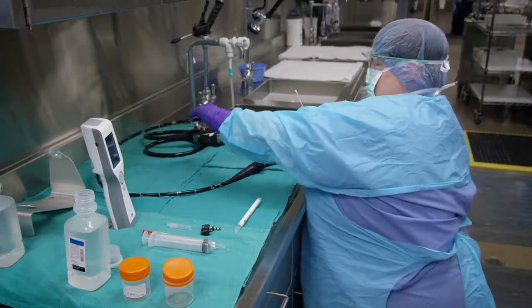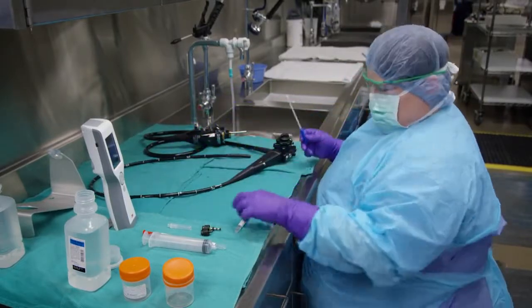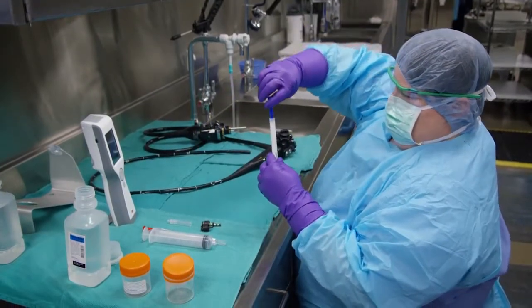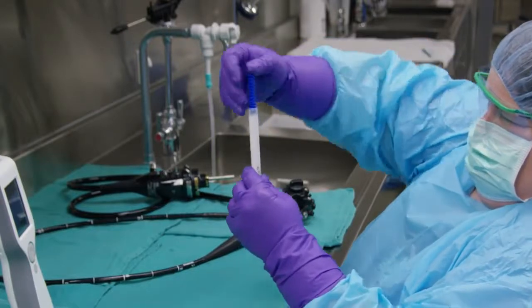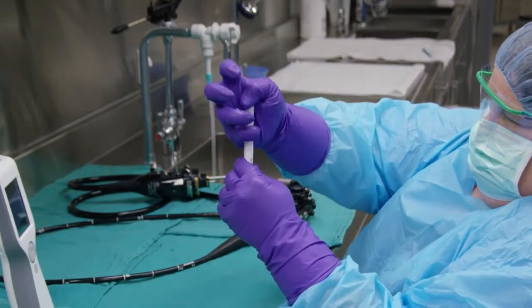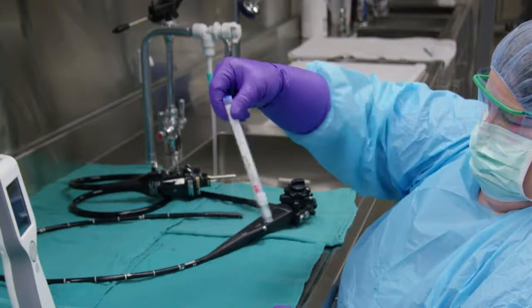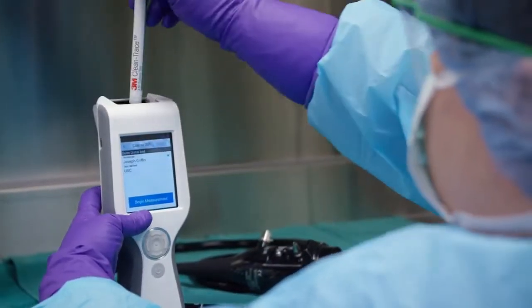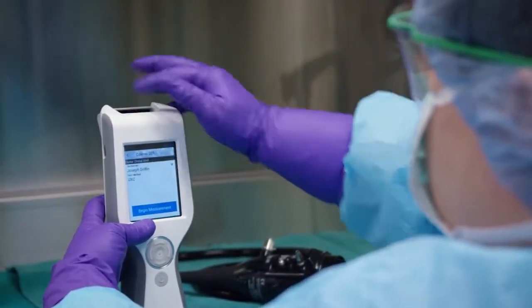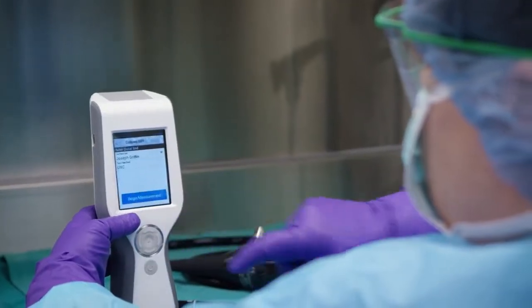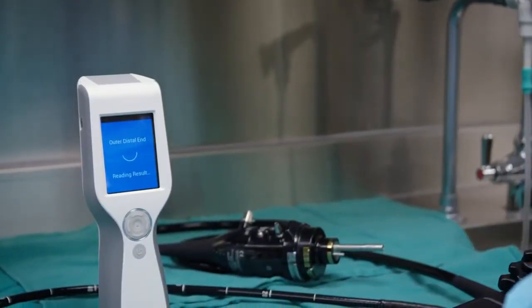AAMI ST91 recommends testing the suction and biopsy channel as a minimum. Tests should be performed during every reprocessing cycle or at least daily for every endoscope used. Results will come within a few seconds. If the scope passes, document and prepare the scope for further processing.